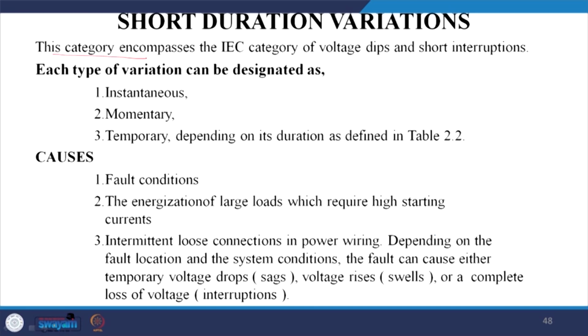Now, let us talk about short duration variations. This category encompasses, as the industrial norm in the IEC, voltage dips and short interruptions. Each type of variation can be designated as instantaneous, momentary or temporary, depending on the duration, as shown in the table here, Table 2.